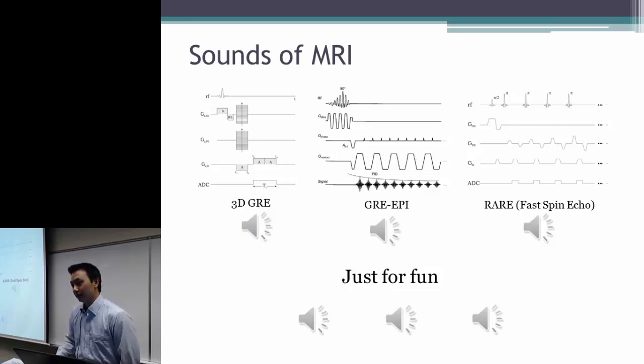That physical vibration inside the magnet you feel during special sequences, such as DTI. Yes, it is the same. The acoustic noise you can hear comes from high frequency vibrations, while what you feel, the whole magnet shaking, is relatively low frequency. You usually feel that with diffusion weighted imaging, because it uses a very strong and very long gradient.